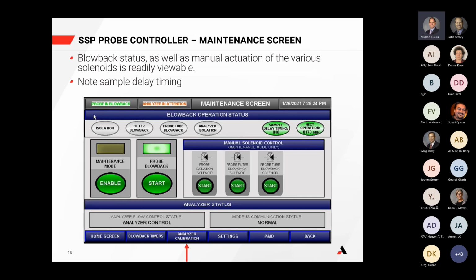I think I might have had that on a slide, Rod. But it will be somewhat dependent on your individual system, because if you've got 50 feet of sample line versus 150 feet of sample line, your sweep time to get to a T90 concentration in the analyzer oven will be slightly different. So that is programmable within the analyzer parameters.